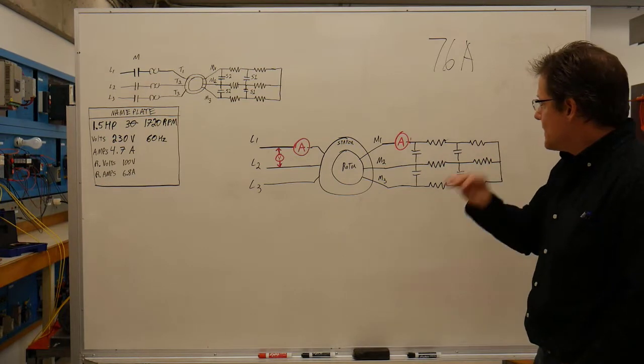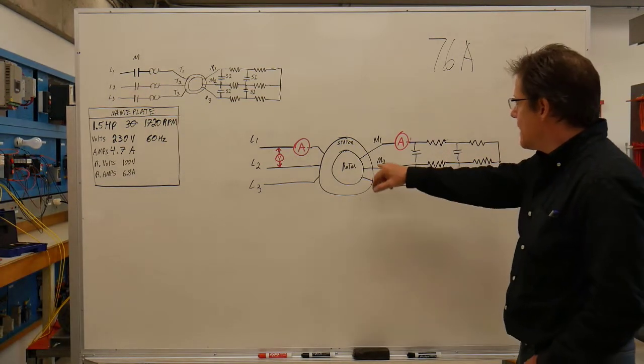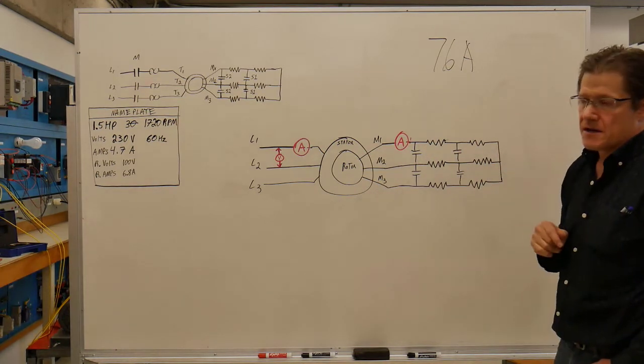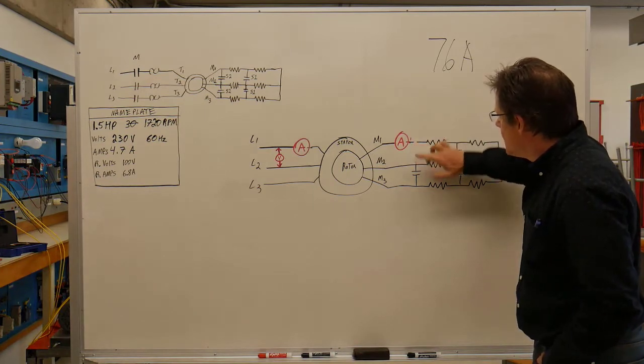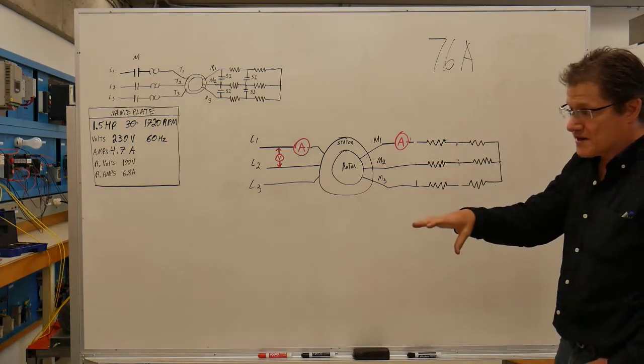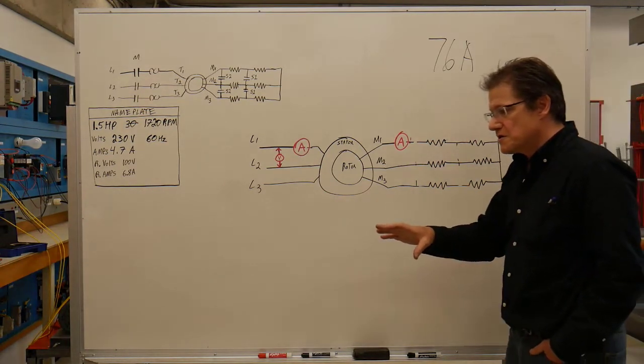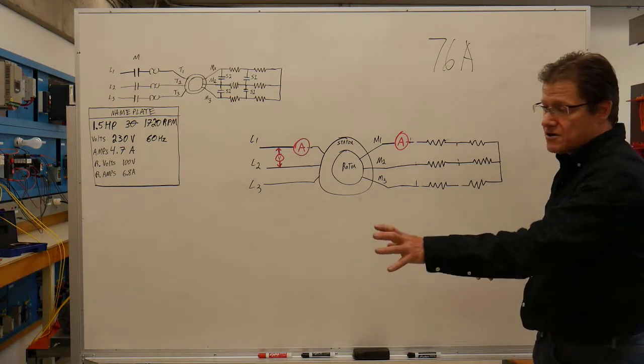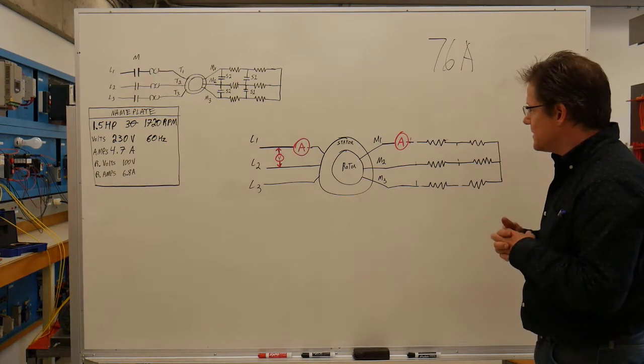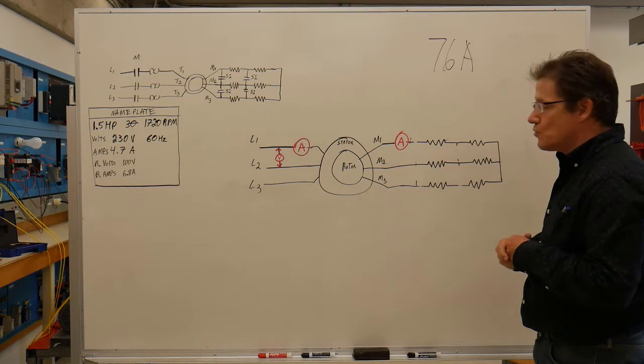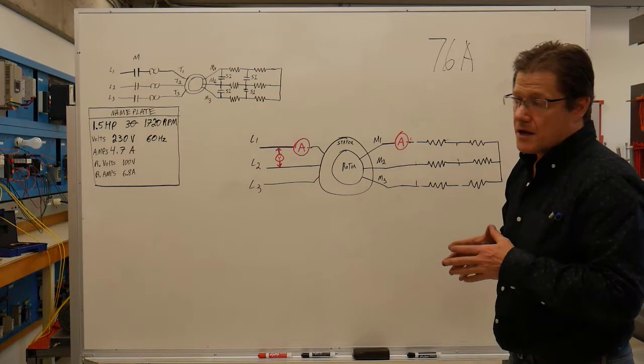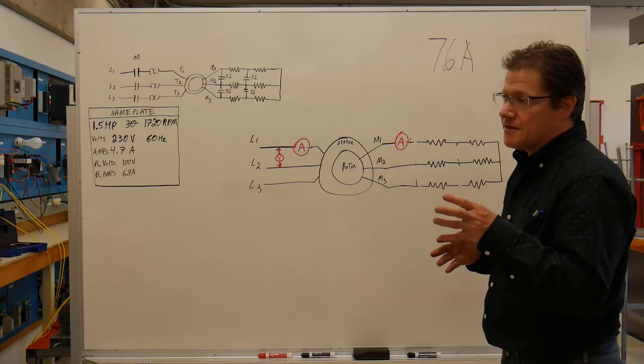Now we've looked at it shorted out and open. We're going to start the wound rotor with all the resistance in the circuit without engaging the bypass contactors. There's not much torque on it, so once it overcomes the flywheel, it'll get up to a decent speed, but not full speed. We'll see how the rotor volts and frequency change as it accelerates.